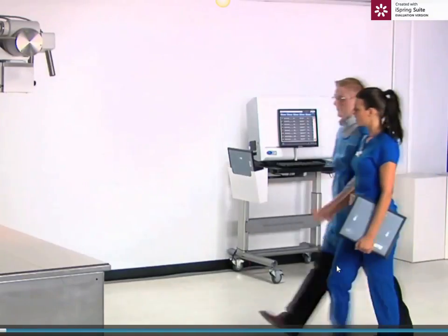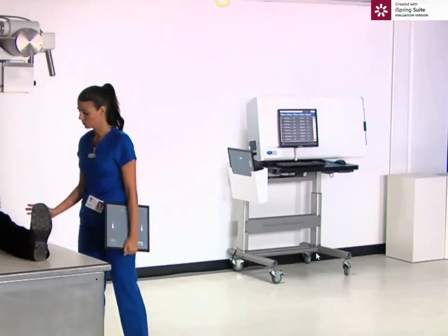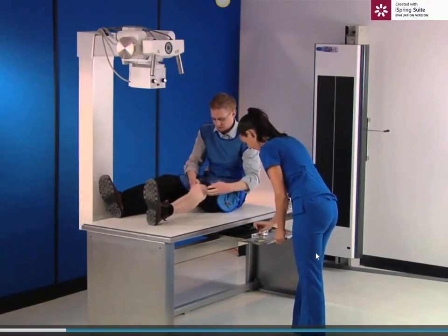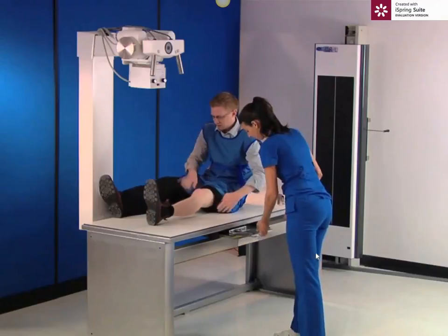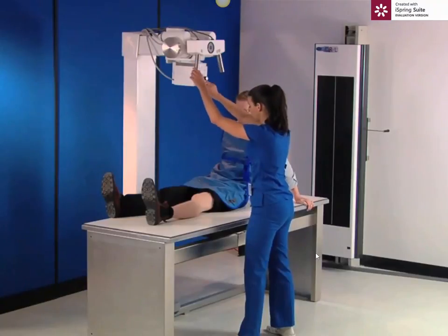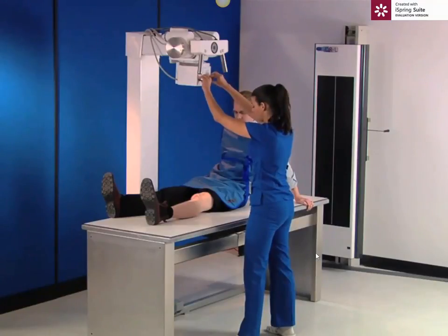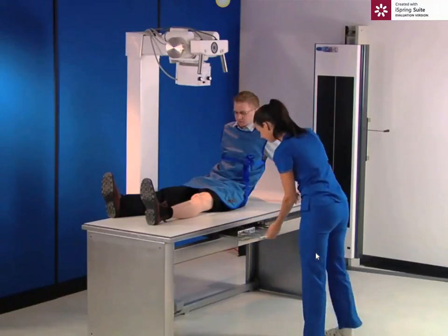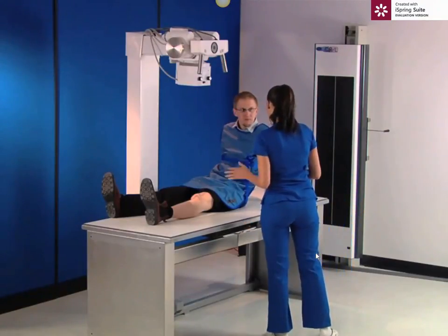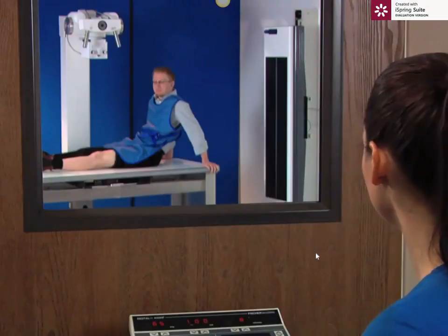ICR 3600 is a computed radiography machine, ideal for general radiology. The system incorporates a true flat scan path technology. This technology ensures the phosphor plate never leaves the cassette to avoid any plate handling, damage, or wear during the scan process. ICR 3600 can read all size cassettes. One advantage of switching to digital with ICR 3600 is uninterrupted workflow. You still take the X-ray of patients the same way using your existing equipment. Only with CR, you can acquire a digital image within seconds, increasing throughput and optimizing patient care.